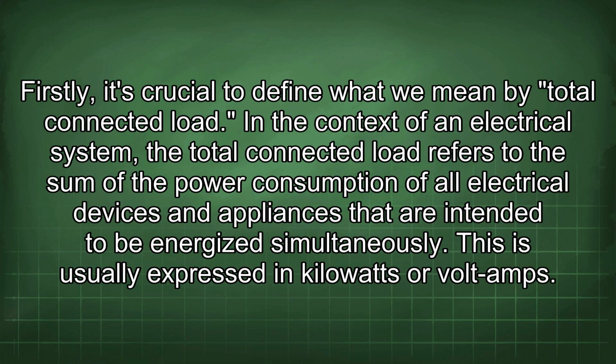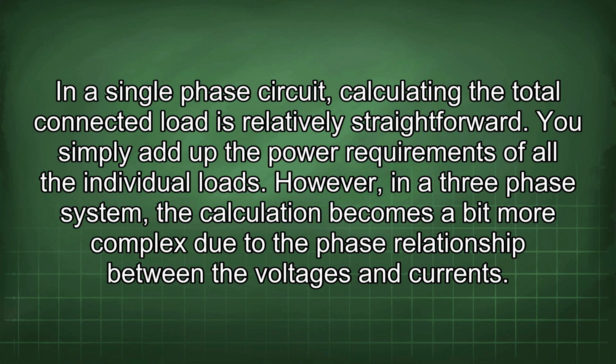Firstly, it's crucial to define what we mean by total connected load. In the context of an electrical system, the total connected load refers to the sum of the power consumption of all electrical devices and appliances that are intended to be energized simultaneously. This is usually expressed in kilowatts or volt-amps. In a single-phase circuit, calculating the total connected load is relatively straightforward. You simply add up the power requirements of all the individual loads.